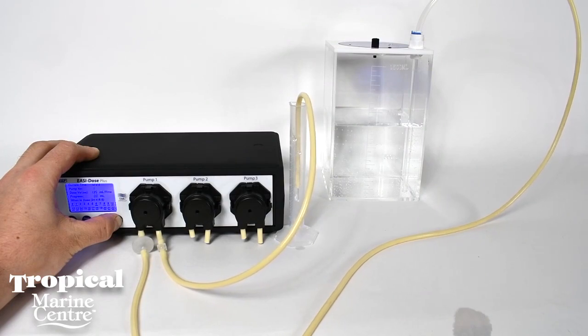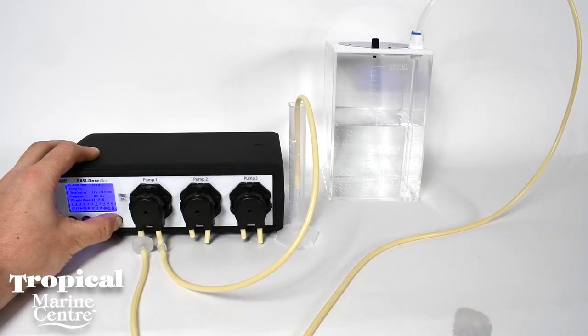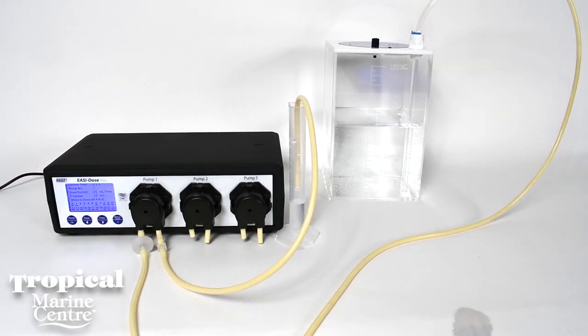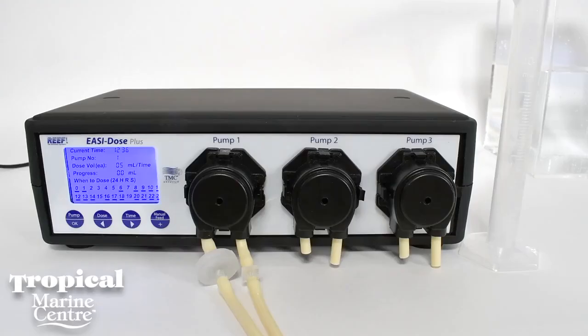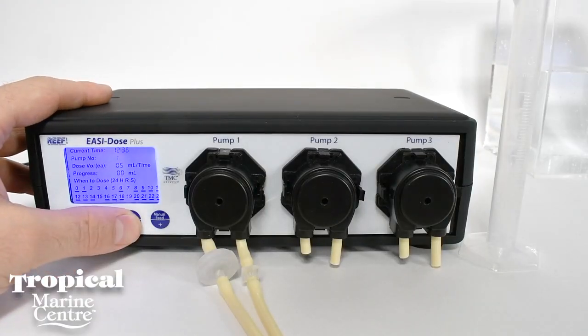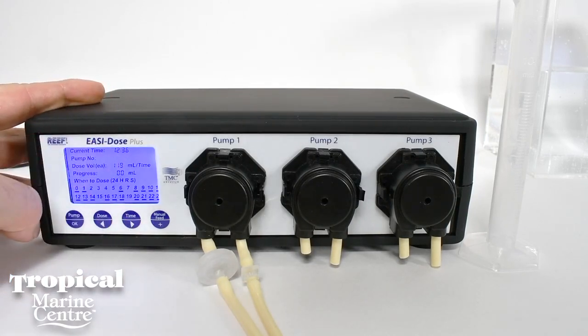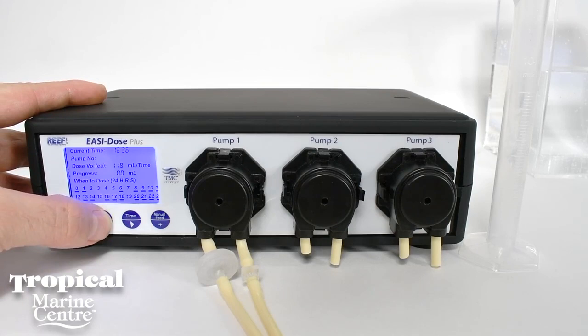Once all the lines have primed, it's time to calibrate the pump. This needs to be done every month to ensure you're dosing a correct amount. At this point, we recommend that you check the hosing in the pump head and replace if necessary. To calibrate, press and hold the time button. This will then start the pump number flashing. This is to let you know you're in calibration mode.